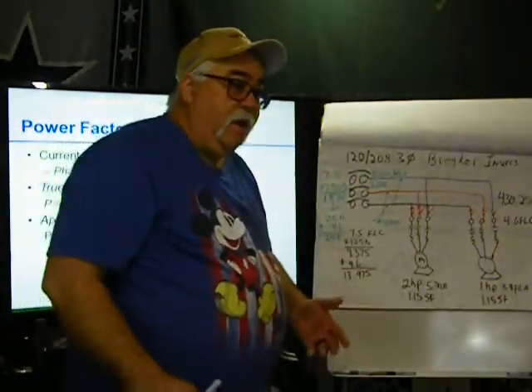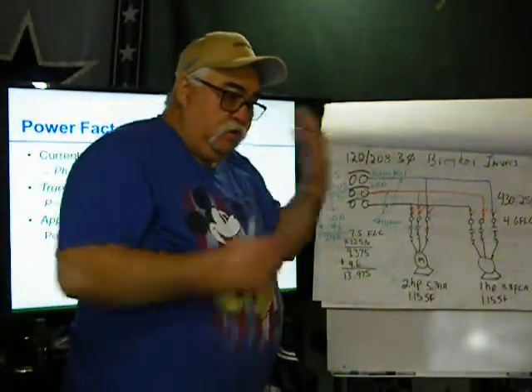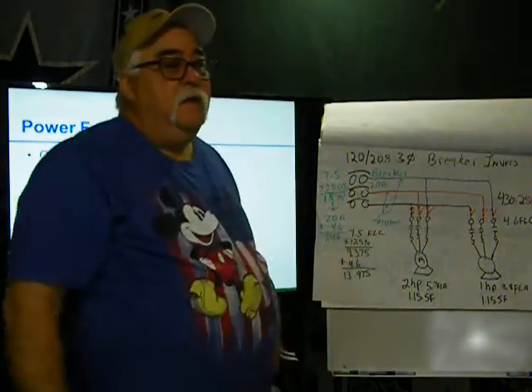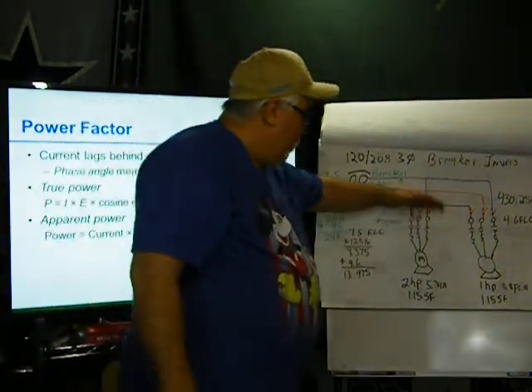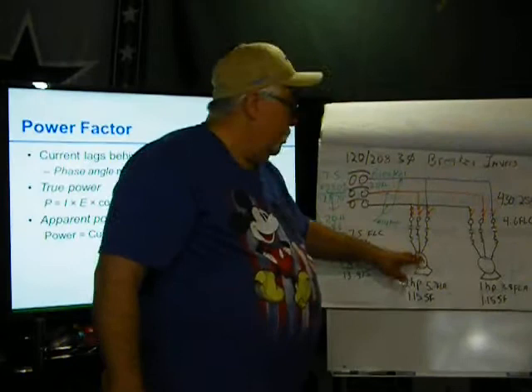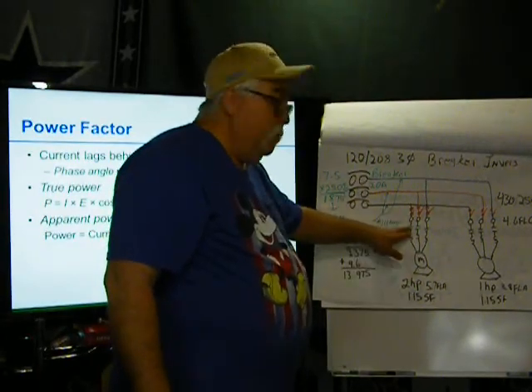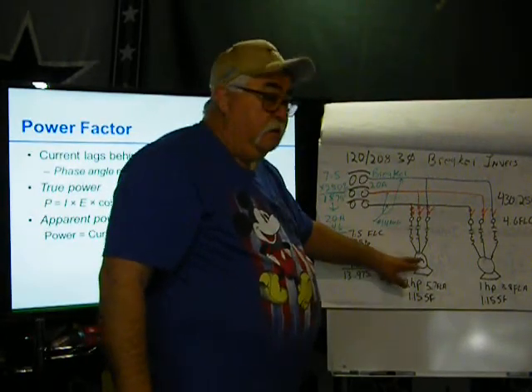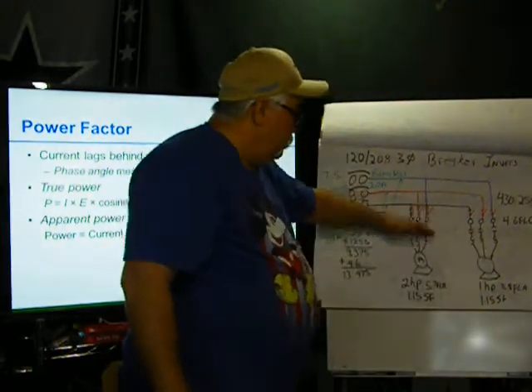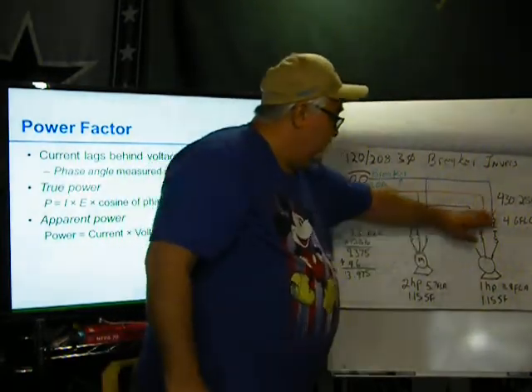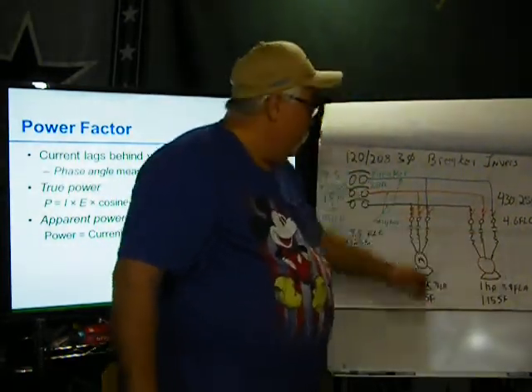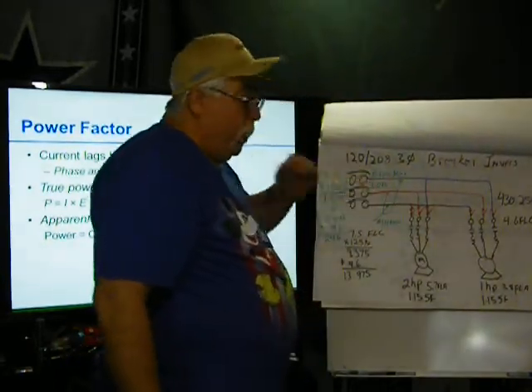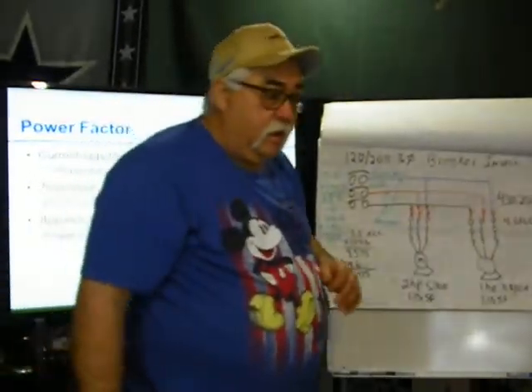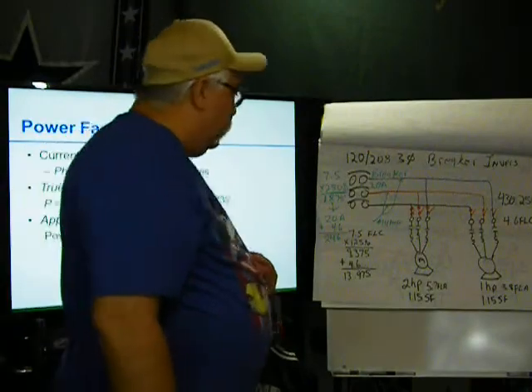I didn't explain that last time. I was just hoping that by seeing the picture you would understand that from here down, it's that single motor and that's it. So my protection here and my overloads here are for that single motor. This one has nothing to do with this, and this one has nothing to do from here down with that. Only with our main wire and our short circuit ground fault protection.